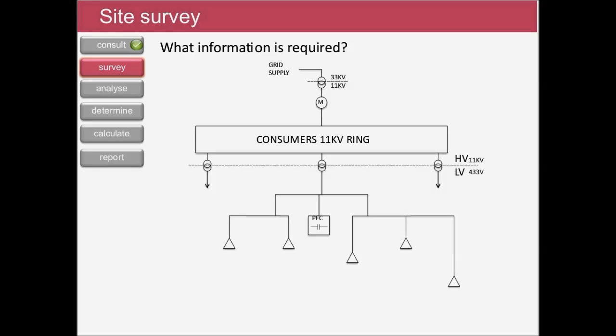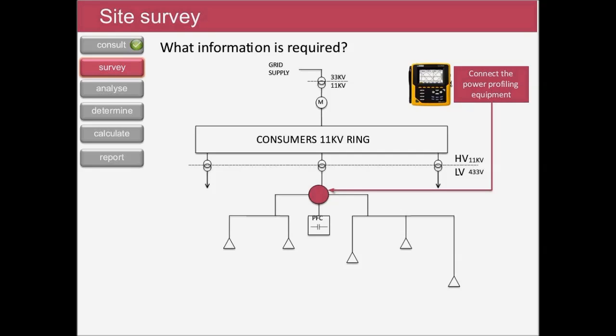So to do that, I've mapped out a simple schematic, and here we can see the grid supply coming in, feeding into the consumer's 11 kV ring, and then we've got three 11 kV to 433 volt transformers, and from the middle one we've attached loads and power factor correction equipment in the middle there. So with all that in place, the power quality meter should be connected at the LV position where the voltage management solution is being considered to be integrated.